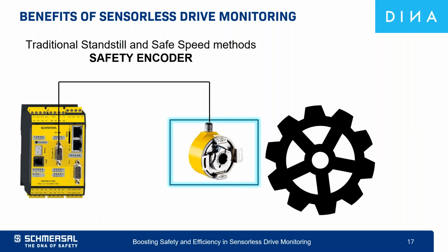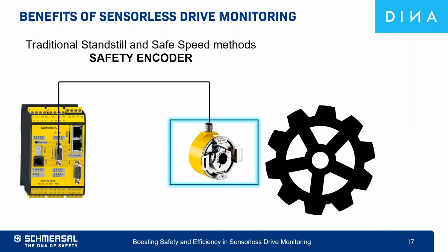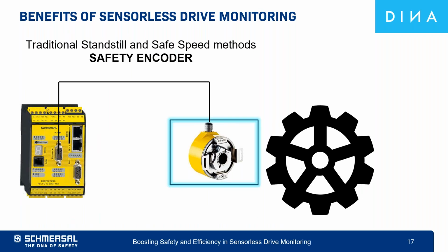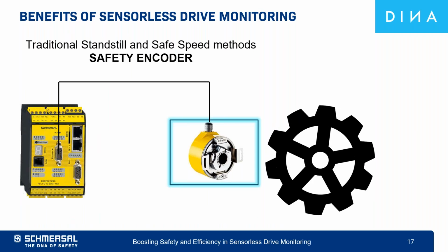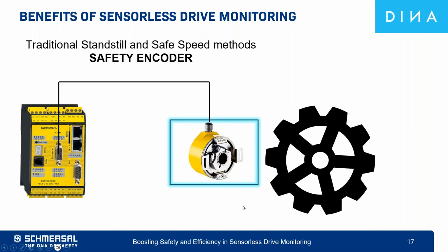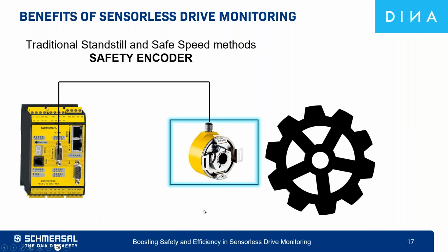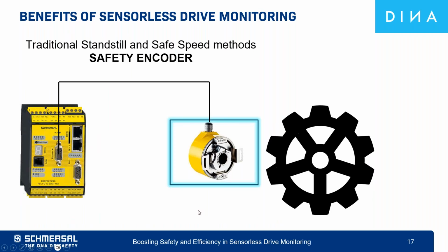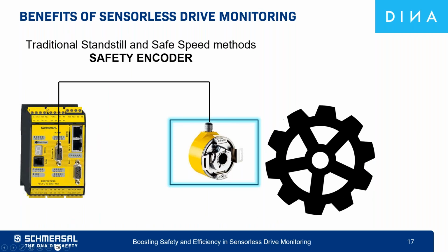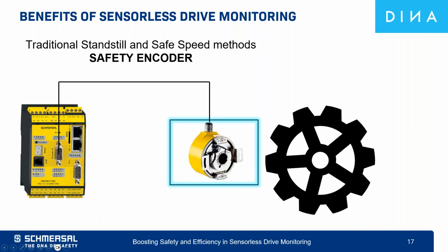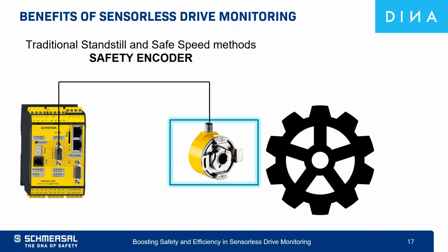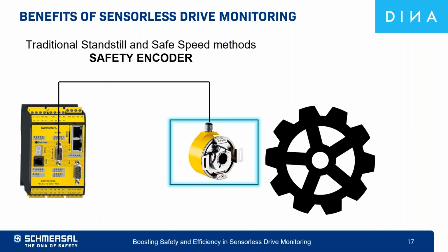In saying this, safety rated encoders do exist now, and while they're expensive, they require less wiring than having two encoders in the field like non-safe encoders. The biggest issue: encoders do have a lifespan. Good quality ones generally have an expectancy of 20 years or 1 billion revolutions. However, working in the machine safety industry, I can tell you I've seen a lot of replacements already, and they haven't been out that long.